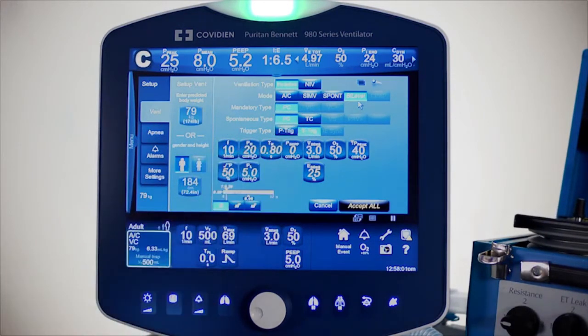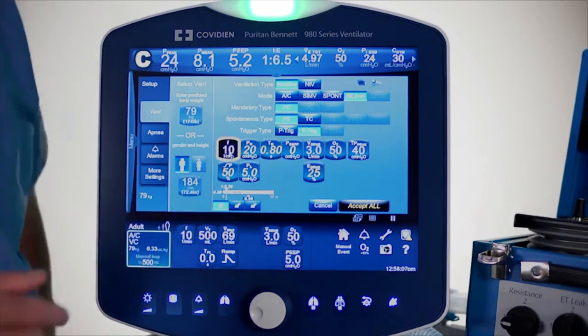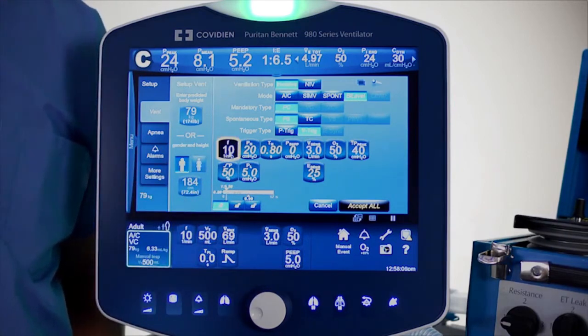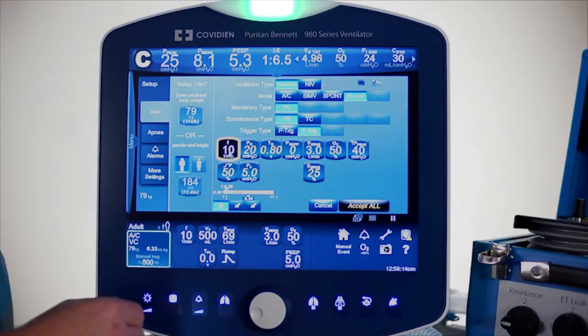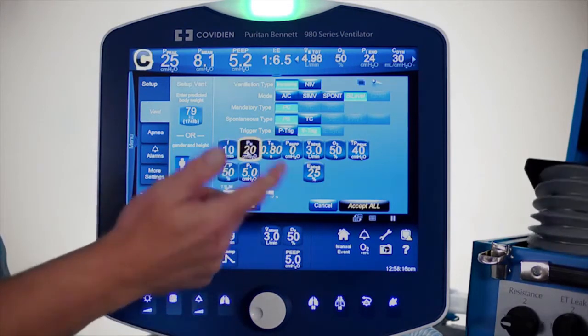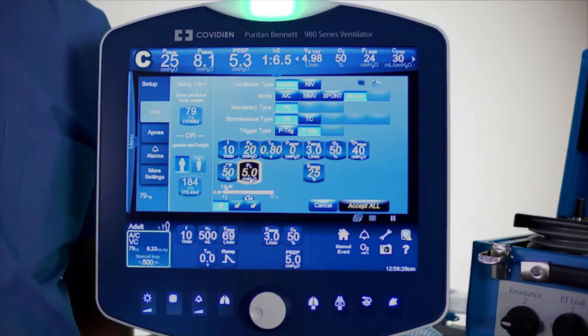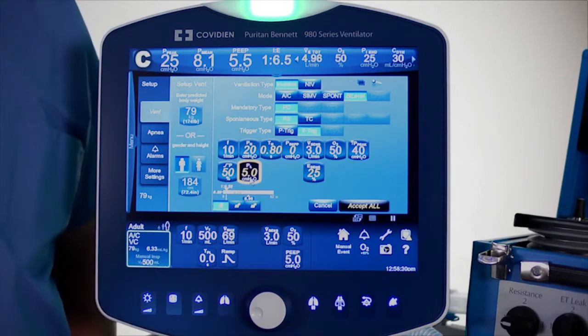You also have types of triggering: pressure and flow triggering. Starting from left to right, you decide the rate — I'll start with a normal ratio at a rate of 10. I have a pressure of 20 over a lower pressure of 5. The upper pressure will be 20 and the lower pressure 5, so the difference between the two determines your total volume. Right now I'm starting off at 15 cmH2O pressure differential.